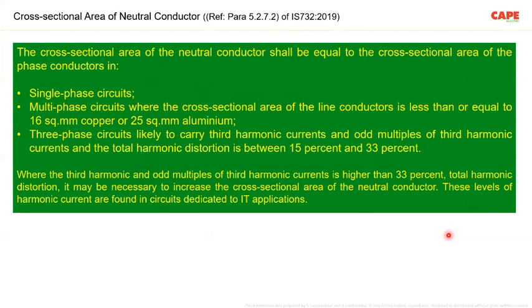The reason I made this statement is that about 6 months back, I saw this in a hospital, especially the wiring which is going to a very critical place. The phase conductor was 10 square mm copper and the neutral conductor was about 4 square mm, and all the equipment are single phase.